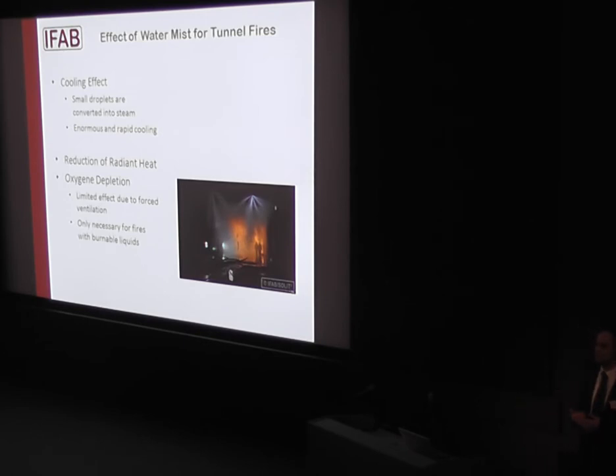Compared to a deluge system, the droplets are still much smaller and provide much better cooling potential. Of course, the aim is to convert these droplets into steam, but the good thing is this will only happen right around the fire — as soon as you're 1, 2, 5 meters from the fire, there's no steam anymore. What we really aim for is an enormous and rapid cooling effect, because heat is one of the biggest issues during a tunnel fire.